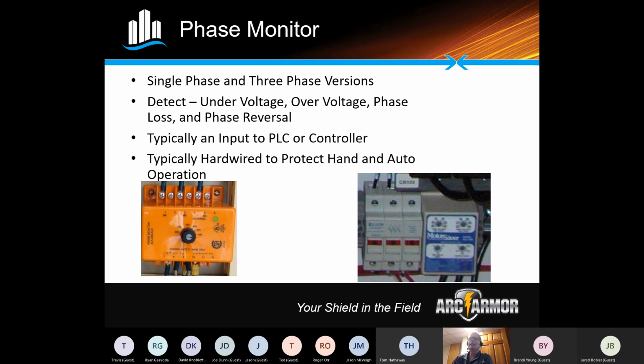Another item that goes hand in hand with the phase monitor, I don't have a slide on it, is also called a power monitor. Power monitors are a little more sophisticated. They have the ability to detect, read, and actually output to PLCs the actual voltage, current draw, and everything associated with that particular panel. But they can also be used to detect undervoltage, overvoltage, phase loss, and phase reversal.